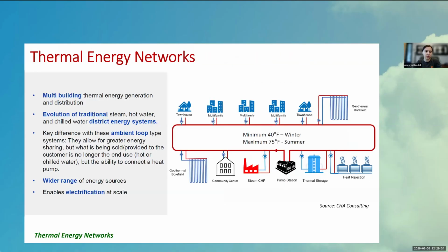This is a slightly more detailed diagram showing some different possibilities for things you can put on a thermal energy network. Going from top right all the way around, you can have your geothermal bore field, which would be a source and a sink depending on what you need seasonally, and then some housing units of different kinds. After all that, your water temperature has changed, either higher or lower depending on the season. You've got a second bore field for another heat source or sink, then maybe some public buildings like a community center, a steam plant, a pump station that pushes everything around, and you could even have thermal storage or extra heat rejection. These are just possibilities — this isn't based on a real system, but you could do something like this.